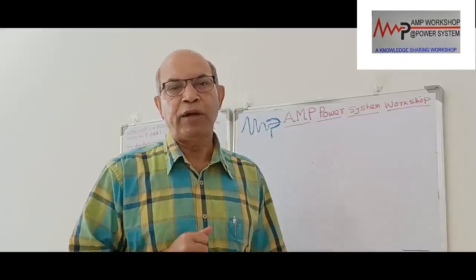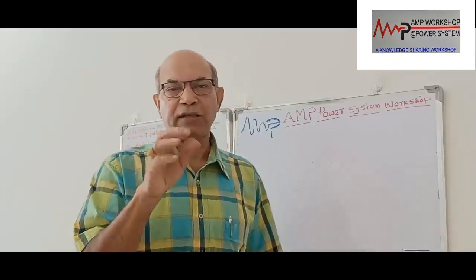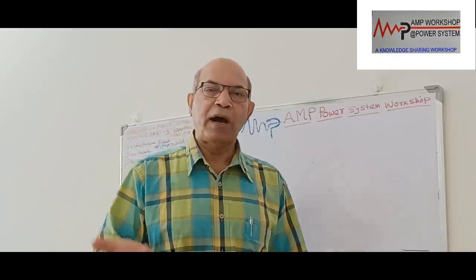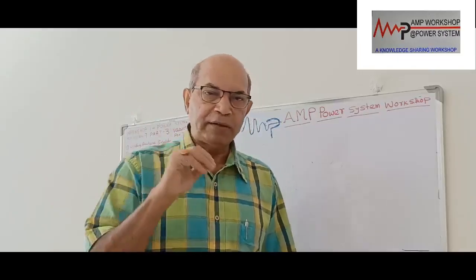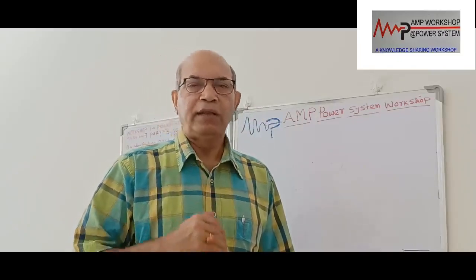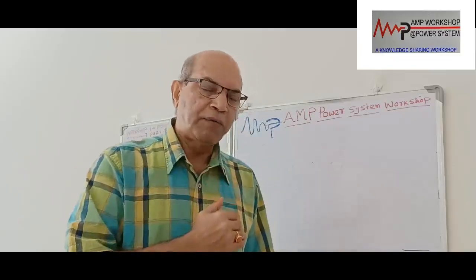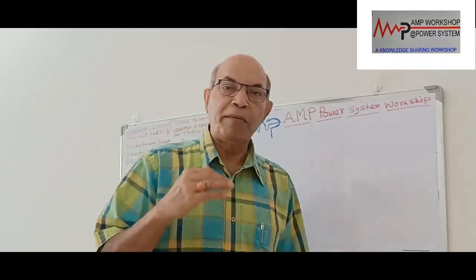First point. Second point, it may happen that crane facility is there, but the access to the transformer is not there. In that case, we have to hire a barge or a heavy vessel with a heavy crane, and with that crane we have to remove the transformer, and then bring it to the onshore. Then after repair, again it will go back to the offshore and be installed. It may take maybe 1 year.